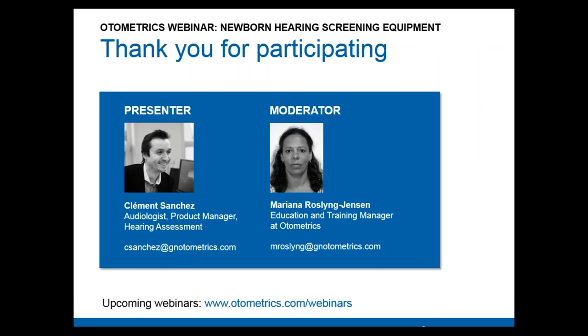To wrap up: when considering acquiring a new immittance solution, keep in mind the probe technology, the probe tip, the size and weight of the probe, and the pump technology. And finally, an increasingly important feature is hygiene and the capability to clean your solution. Thank you very much.